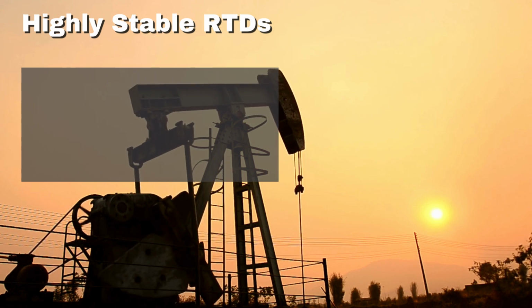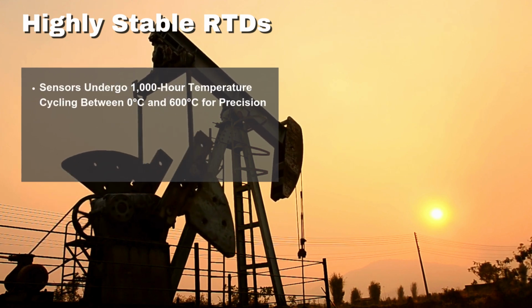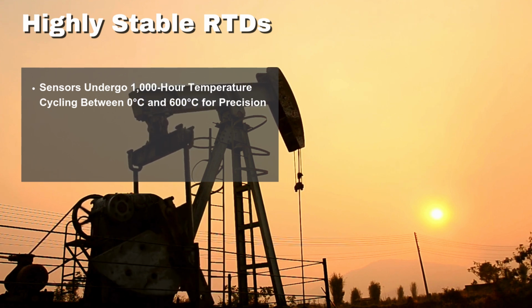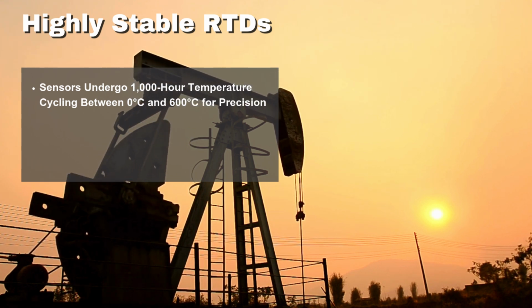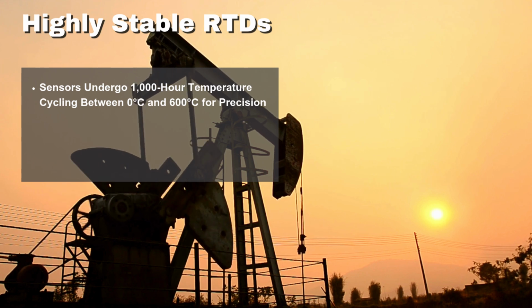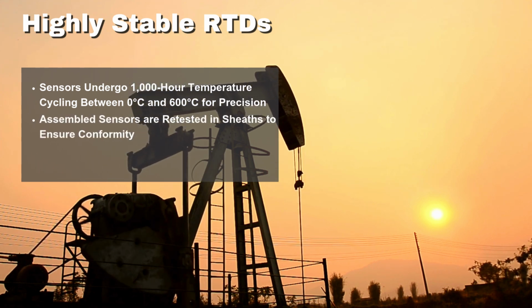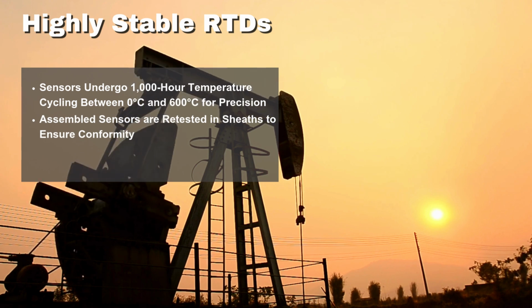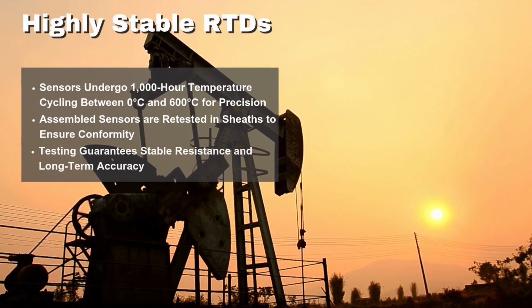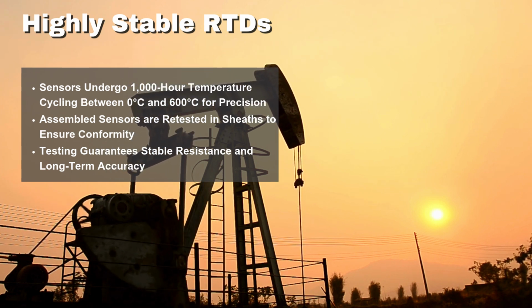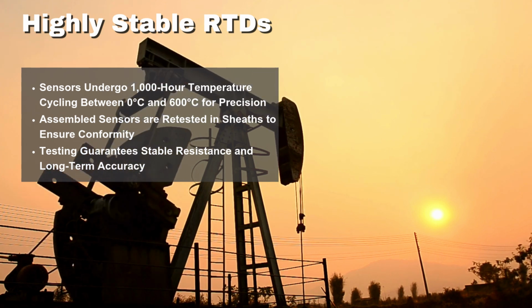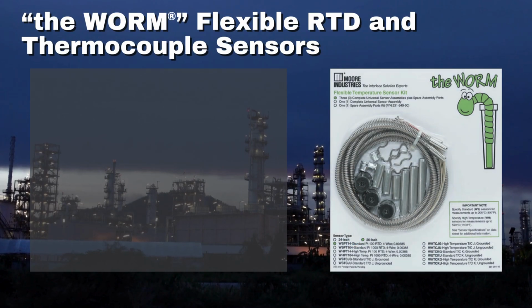Additionally, Moore Industries' highly stable RTDs undergo rigorous testing to ensure precision and long-term performance. Each sensor is temperature cycled for 1,000 hours at 0 degrees Celsius and 600 degrees Celsius to meet strict precision standards. Once assembled into a sensor sheath, the sensors are cycled again to pass a conformity test. Testing ensures stable resistance and accurate coefficients for long-term performance. The worm flexible RTD and thermocouple sensors set the standard for our temperature assemblies.